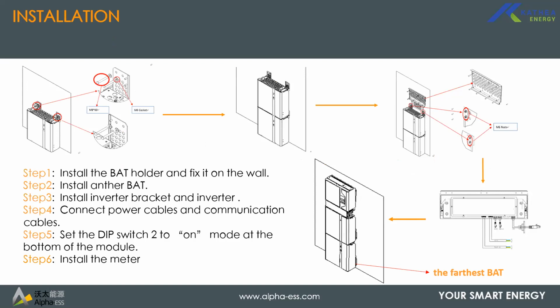So on the installation, the system is quite heavy, so it's recommended that the system sits on the floor or on a platform which can take much load. So the first, as you can see from our top left to the right, you have to sit your battery on the floor against your platform you're installing it. We'll refer to your wall in this example. So you sit your battery on the floor against the wall with brackets provided.